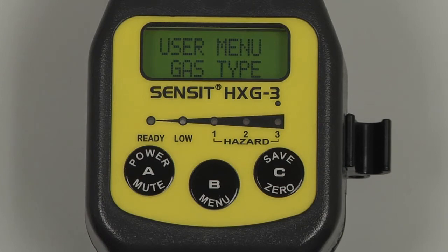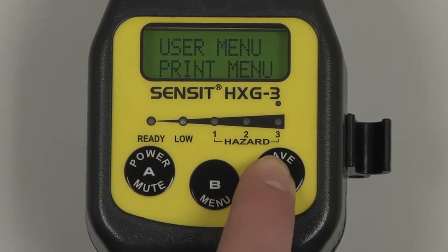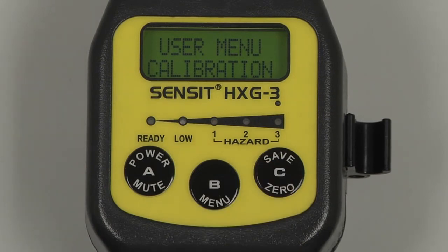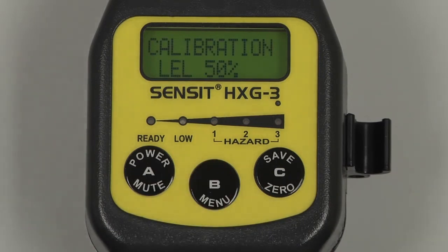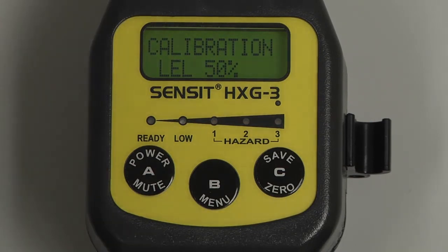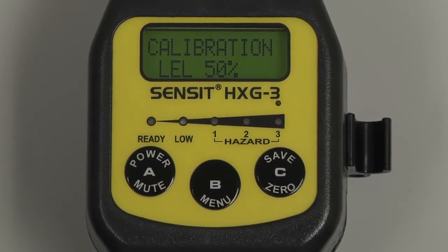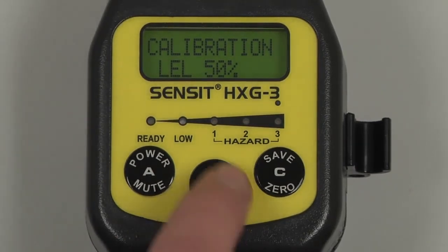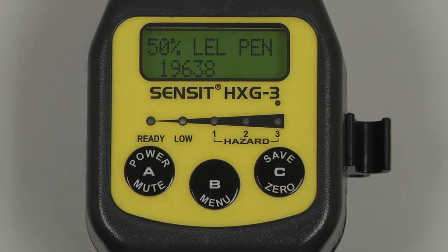And if we wish to perform a calibration, we can scroll through with the C button until calibration appears. Select by pressing and releasing the B button. Attach the regulator to the calibration gas. Turn on the regulator. And attach the cal adapter to the end of the gooseneck. Select by pressing and releasing the B button. And pentane calibration will begin.